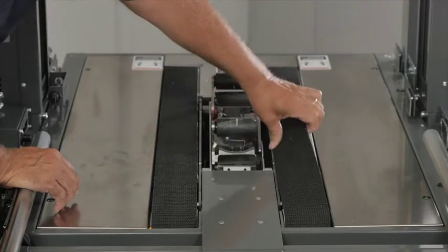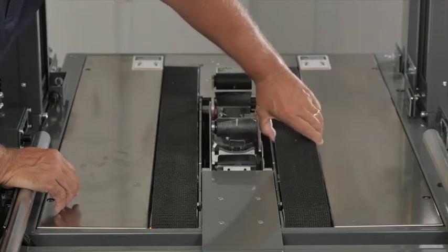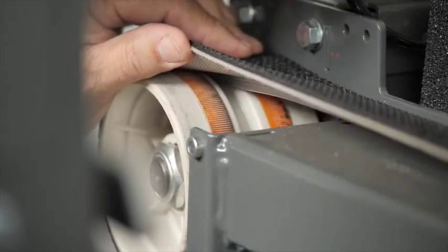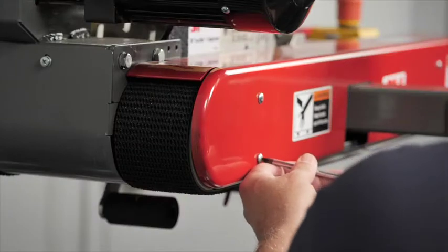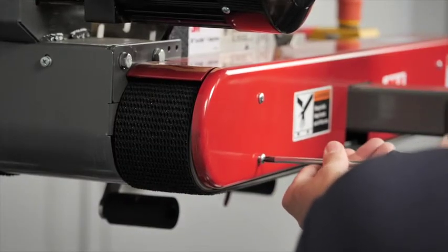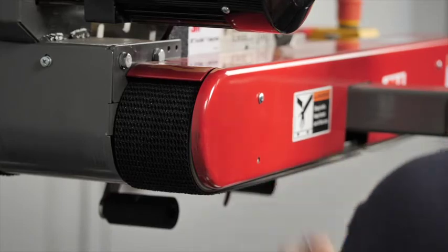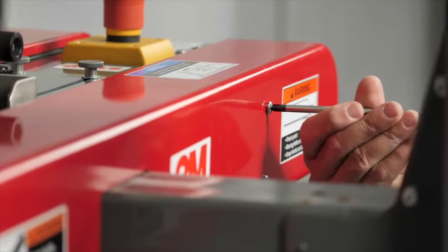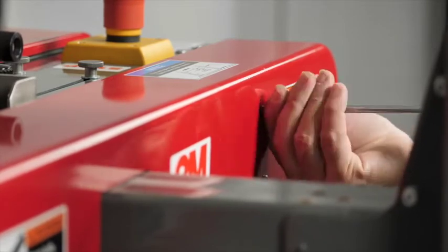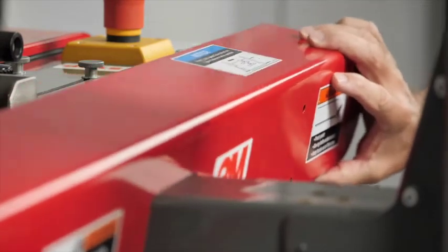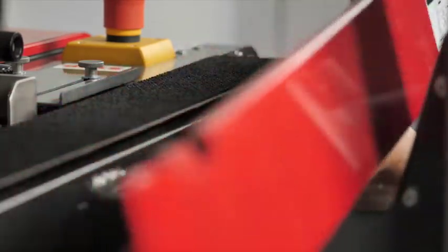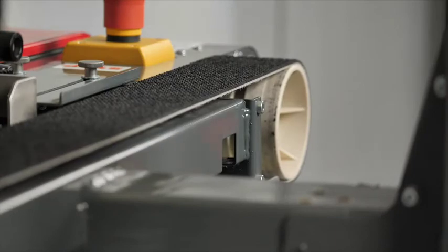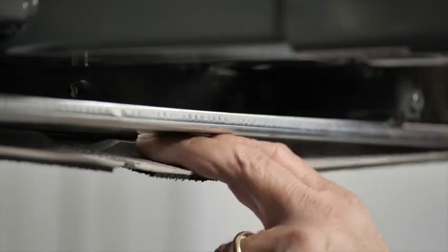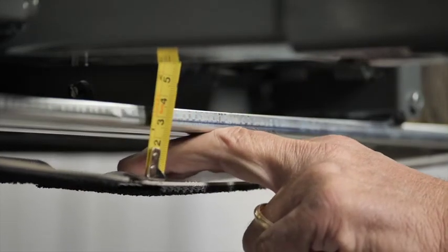Check to make sure the drive belts and orange friction rings are clean and not worn. Replace as necessary. If replacement is necessary, remove the guards. Belt tension can be obtained by tightening the adjustment screw so that a moderate pulling force of 3.5 kilograms or 7 pounds applied at the midspan will deflect the belt 25 millimeters or 1 inch.